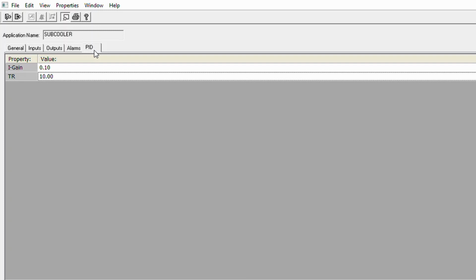This is why I took that update rate from 10 seconds down to 2 seconds, because now you're going to be looking at the loop every 2 seconds. 10 seconds is really long for a PID, or a PI loop. We aren't running PID loops. The majority of what you're going to do in refrigeration is just PI loops. We don't need D. We don't need it thinking over time that much. We just need short changes over time where the I comes in. But you're going to have to tune these. Do not run the stock settings. You're going to flood out or you're going to have very poor control.